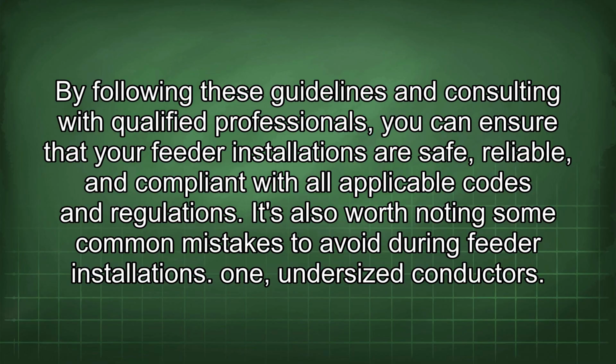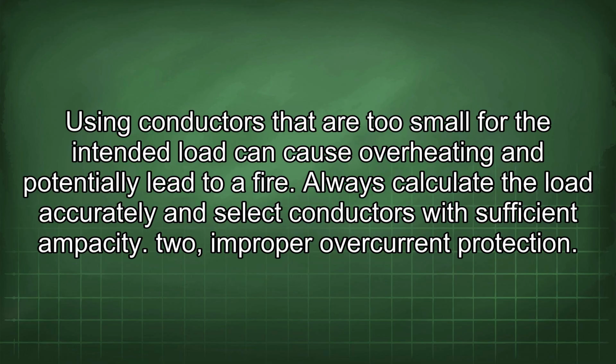It's also worth noting some common mistakes to avoid during feeder installations. 1. Undersized conductors. Using conductors that are too small for the intended load can cause overheating and potentially lead to a fire. Always calculate the load accurately and select conductors with sufficient ampacity.